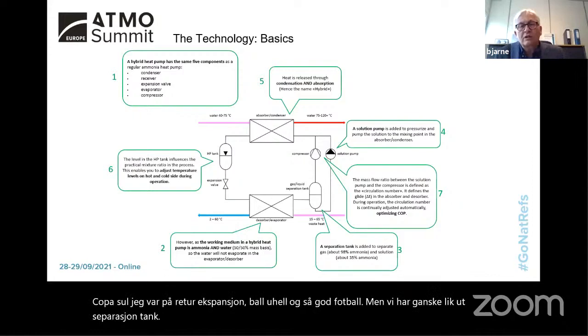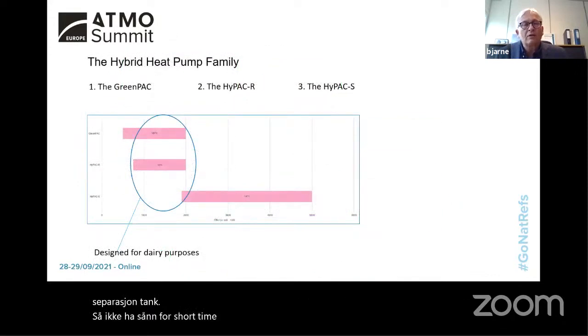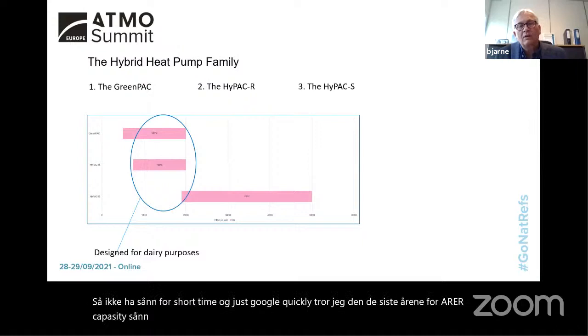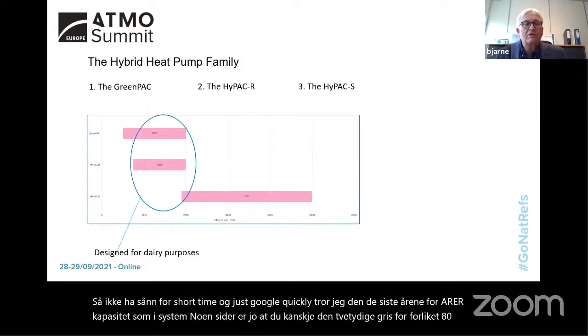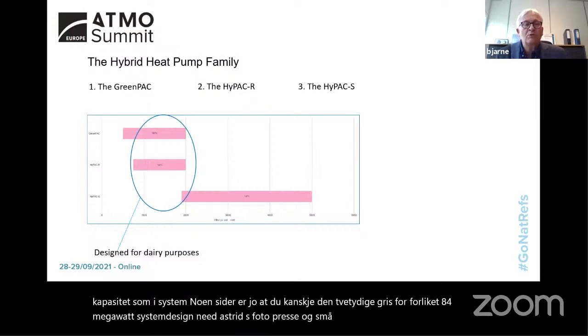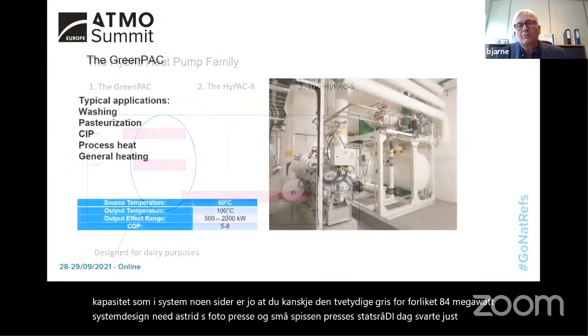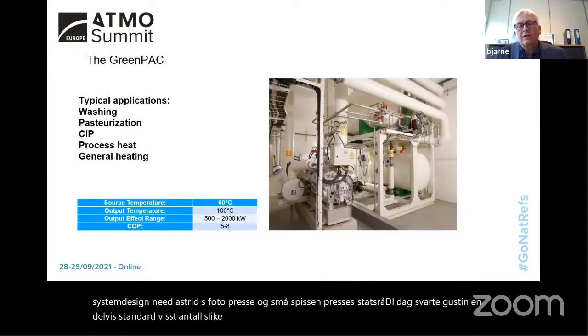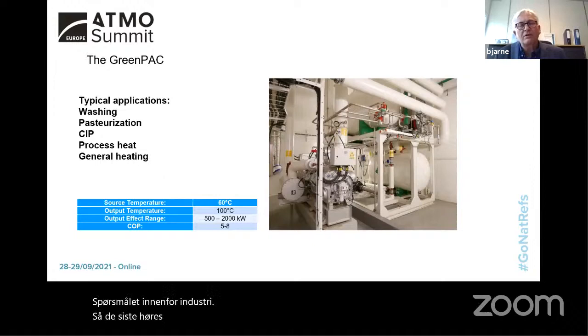Because of the short time, I'll go very quickly through this. This is the range of capacities for this system. You can see it can go up to 120 degrees for systems up to 5 megawatts, but that requires a screw compressor. For smaller systems we use piston compressors - that's what we used in the dairies. Standard piston compressors, like you see on the left side, are very frequently used in the industry, especially in the food industry. Here we used the Sabroe compressor.